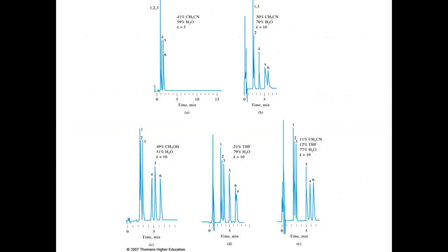HPLC guard column and column HPLC. Yes, so guard column, explain once. Guard column is also called a pre-column, which is used to remove any irreversibly bindable solute present in the sample or any unwanted species present in the mobile phase. These guard columns are placed before the analytical column or after the injection port. The stationary phase present in the guard column will be the same as the analytical column, and sometimes it may be different. Analytical. Okay.